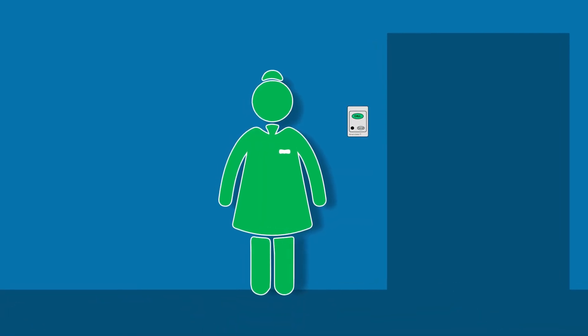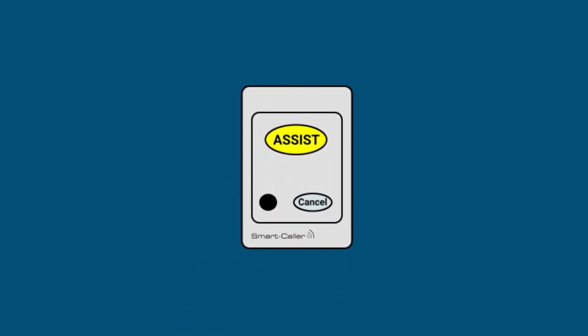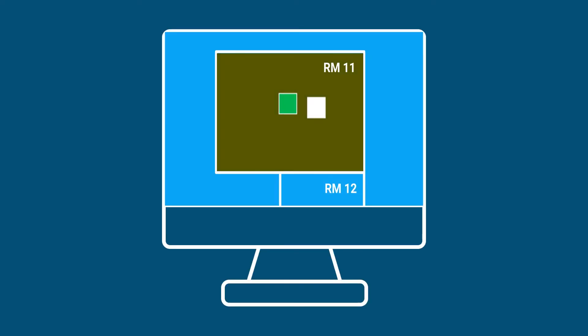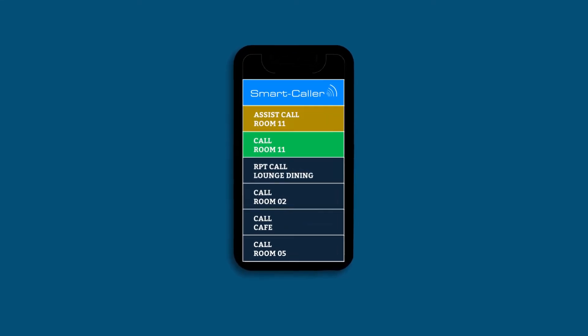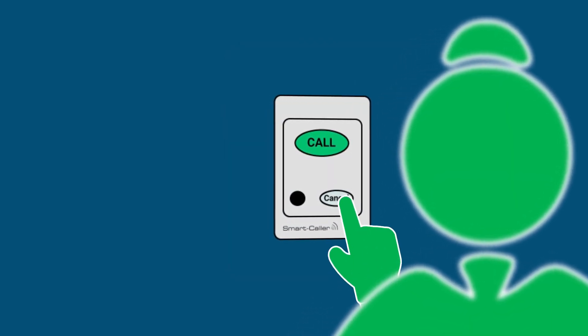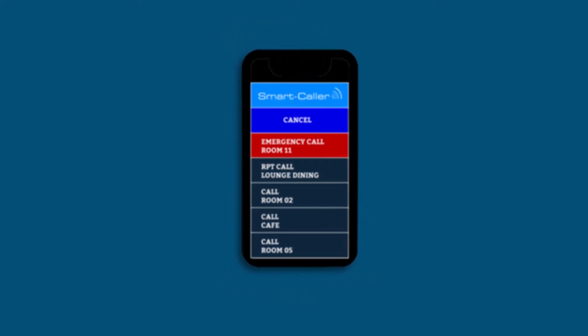Let's now develop the theme to suggest that Nurse Jane needs assistance. By simultaneously pressing both the call and cancel buttons on the en suite call point, the call has now been escalated to the higher priority of staff assist. This also changes the colour of the graphic display location to flashing yellow. By the way, these various colour and tone priority identifiers are carried through to also occur within both fixed and mobile displays programmed to receive these calls. If Jane had not escalated the priority of the call, the existing presence status would have been terminated by Jane pressing the call point's button, in which case a brief cancel message will appear on all portable display devices. Automatic cancelling is also possible but is not recommended for many valid reasons.